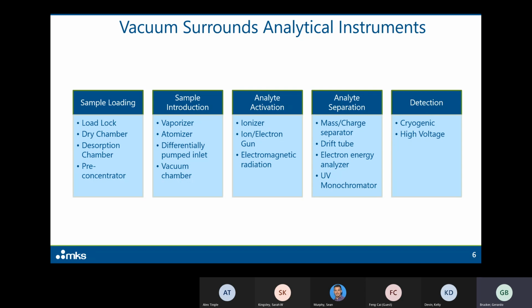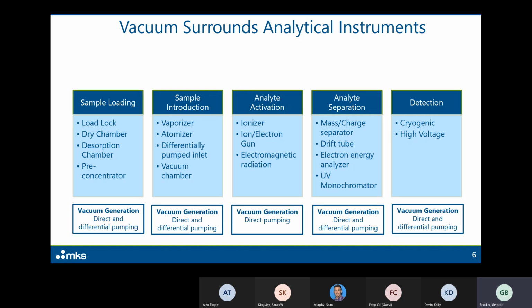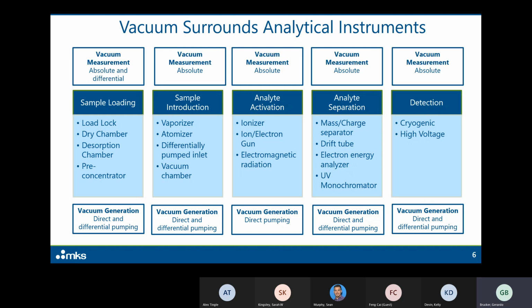So again, vacuum is required as we go through the different sections. Vacuum is required in all of them for different reasons, but it's still needed, and vacuum control is very important. And of course, in some instruments there is often a dedicated set of vacuum conditions for a detector, maybe because it is a cryogenic detector or a very high voltage detector, in which case we have to prevent arcing. No matter what, every one of these stages requires vacuum generation, which could be direct or differential pumping. And in all of these cases, we need vacuum measurement.